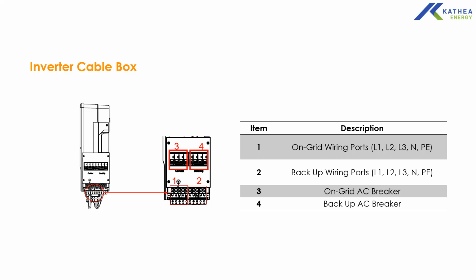So try and avoid inductive loads, and try and avoid connecting DC loads on the AC bus. Let's say on the output of the inverter, you connect a UPS. A UPS is basically a DC load, because it will take the AC out of the inverter and convert it to DC to charge those batteries. So if your battery bank is big, you find a situation where the system gives you a DC high inject fault, meaning that on your AC load there is a DC component. So those are some of the things you need to look at when you're speccing the system.